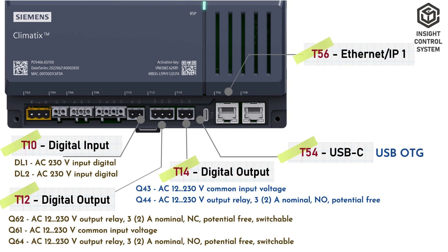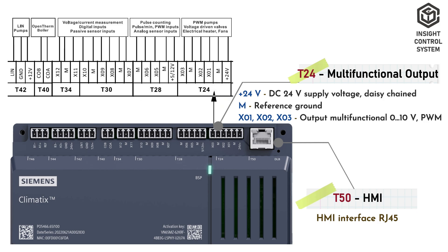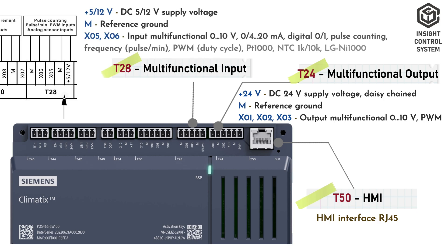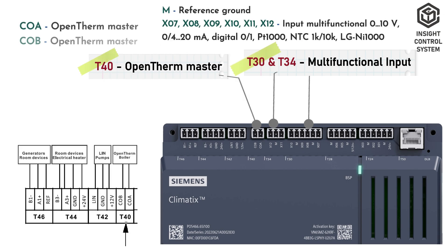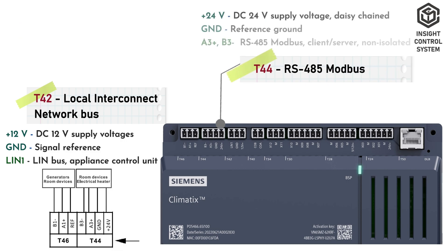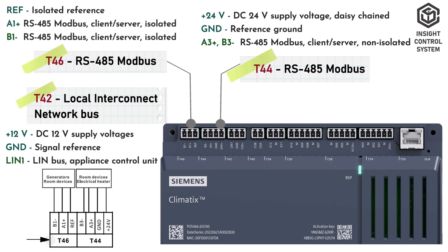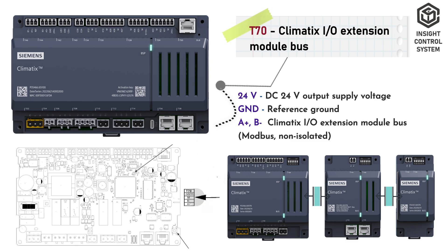Terminal T14 is digital relay output for potential-free relays. T54 is USB OTG port. T56 is Ethernet IP1 port. T58 is Ethernet IP2 port. T50 is RJ45 HMI interface port. Terminal T24 is multifunctional outputs and DC 24 volt supply voltage for daisy-chained devices. Terminal T28 is pulse width modulation inputs and DC 5 or 12 volt supply voltage. Terminals T30 and T34 are multifunctional input ports. Terminal T40 is OpenTherm master for thermostat controls. Terminal T42 is local interconnect network bus port. Terminal T44 is RS485 Modbus client/server non-isolated and DC 24 volt supply voltage for daisy-chained port. Terminal T46 is RS485 Modbus client/server isolated port. T70 is DC 24 volt output supply and Climatix I/O extension module bus.